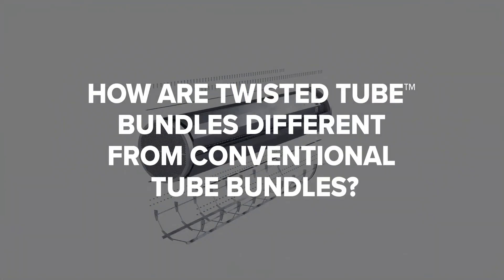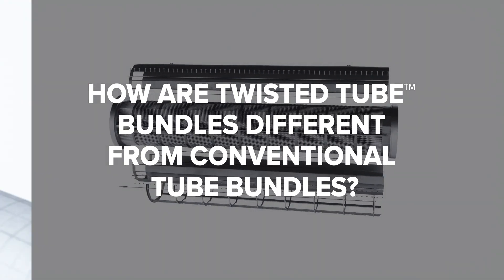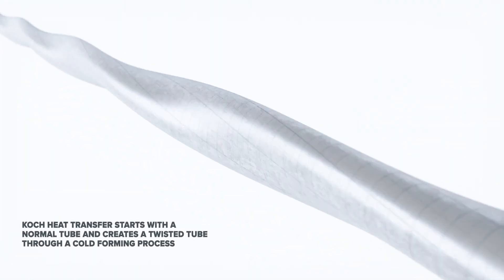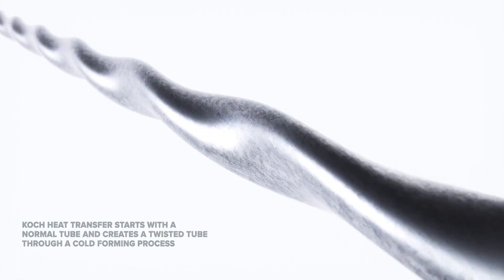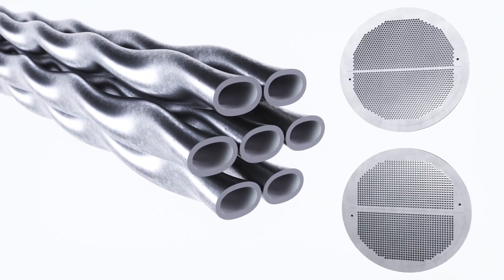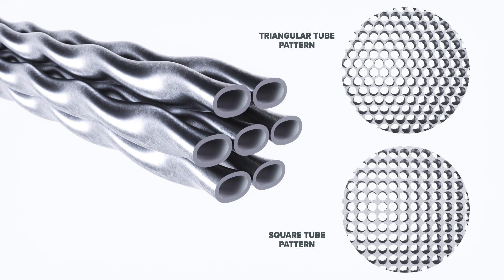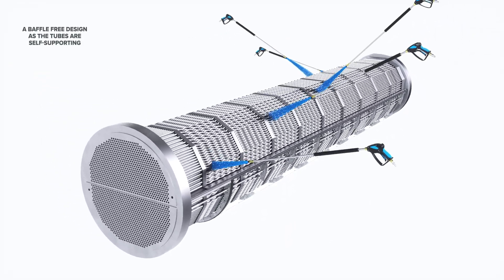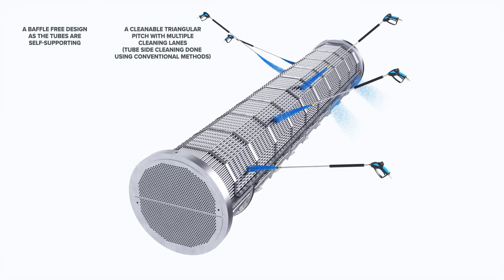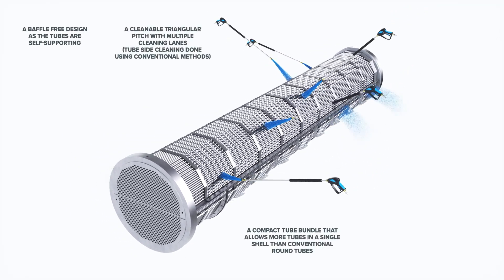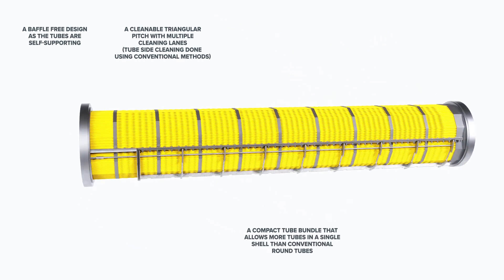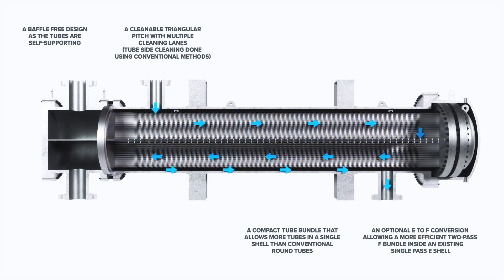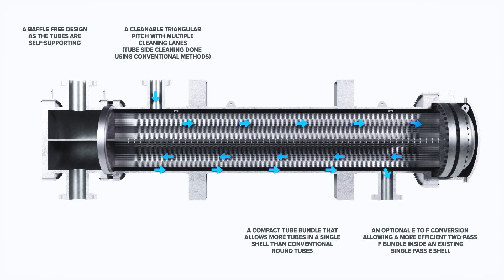How are twisted tube bundles different from conventional tube bundles? Koch Heat Transfer starts with a normal tube and creates a twisted tube through a cold-forming process. When these tubes are grouped together, they form a triangular tube pattern as opposed to the square tube pattern found in many conventional tube bundles. The triangular tube geometry allows for a baffle-free design as the tubes are self-supporting, a cleanable triangular pitch with multiple cleaning lanes, a compact tube bundle that allows more tubes in a single shell than conventional round tubes, and an optional E to F conversion, allowing a more efficient two-pass F bundle inside an existing single-pass E shell.